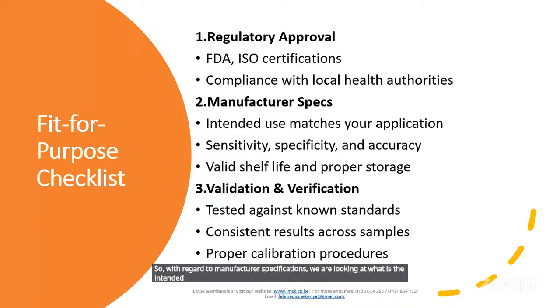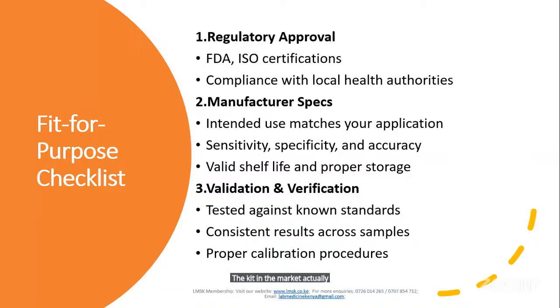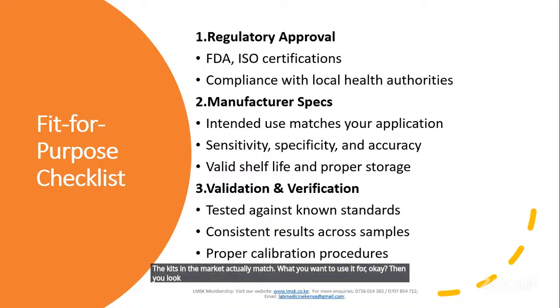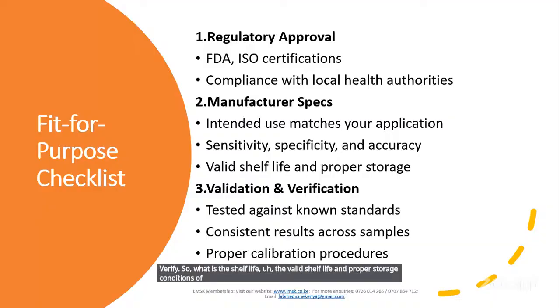So with regard to manufacturer specifications, we are looking at what is the intended use. Does the kit in the market actually match what you want to use it for? Then you look at the sensitivity, specificity, accuracy or precision of these kits. Of course, we are basing on what the manufacturer is putting forth, because at the end of the day, we shall have to verify. So what is the valid shelf life and proper storage conditions of these kits? Can we meet the requirements?